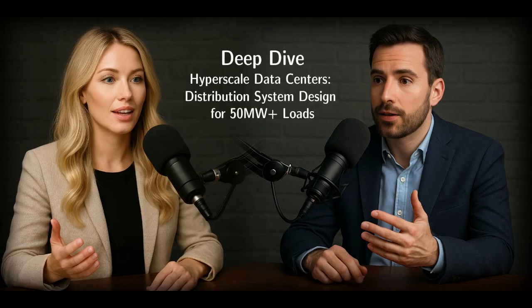So boiling all this down, if an engineer is faced with these large data center requests today, what are the practical go-to design guidelines that emerge from this analysis? Okay, let's summarize. For loads roughly in the 15 to 35 megawatt range, the recommended approach is generally a dedicated 25 kilovolt distribution substation. Feed it radially, but with automatic transfer capability to a backup source if possible. Use enhanced distribution protection, definitely designed for N-1 reliability on the transformer's minimum, and include those load tap-changing transformers for power quality. Got it. And for the next tier, say 35 to 75 megawatts.